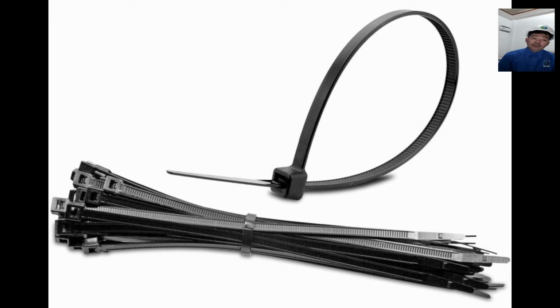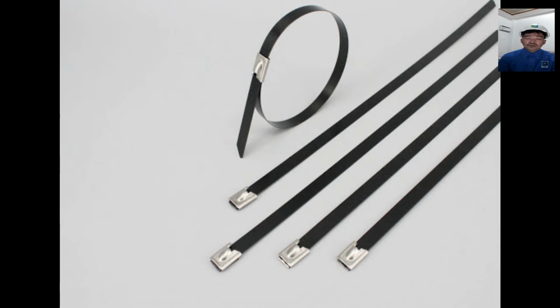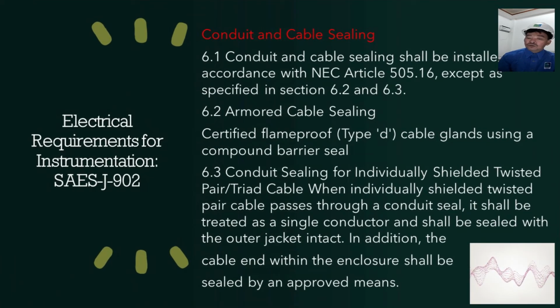So the cable ties are very important in instrumentation, because if you use poor quality cable ties, they will not last long. This will affect your cable dressing, and they will be damaged easily by the temperature. Regarding the conduit and cable sealing, this is a special process in electrical. Take note of that.